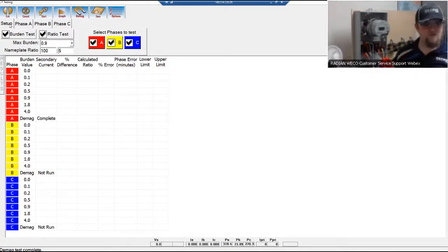So while you're running the CT test, the only thing you need to move is this probe. You do not need to move anything on the RW. You can leave the RW sit as is, voltage and current in line, primary probe moving only during the test. You do not need to touch anything on the RW during the test. So if I wanted to start my RW's CT test, I'll go ahead and hit start over here.